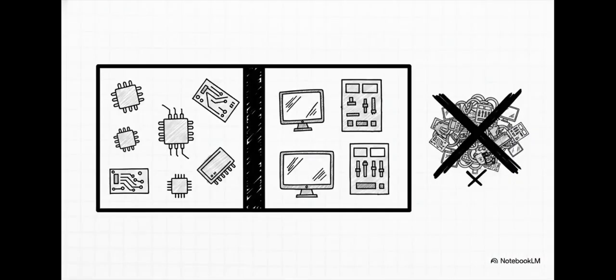And I want to pause right here and be incredibly direct for a second, because this is a non-negotiable best practice straight from Siemens. You must default to total segregation. Use a station granular structure. That means exactly one user project per station. Why? Because when you finally hit the commissioning phase, mixing AS and OS objects in one project creates endless workflow bottlenecks and massive headaches. Total segregation gives you the maximum flexibility you are going to need later on.